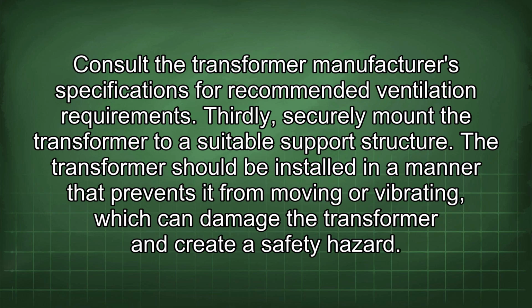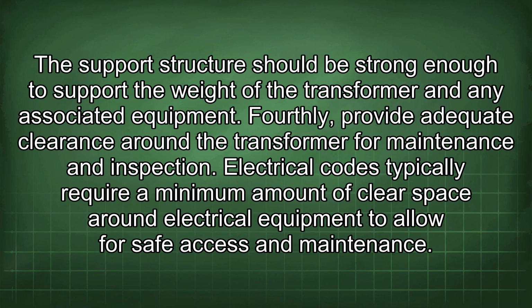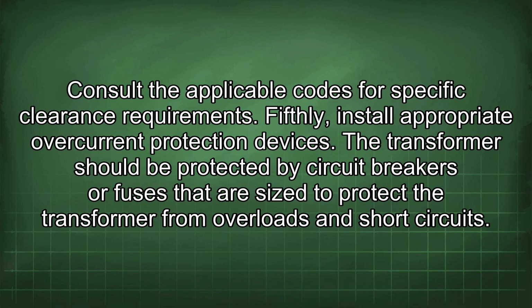Thirdly, securely mount the transformer to a suitable support structure. The transformer should be installed in a manner that prevents it from moving or vibrating, which can damage the transformer and create a safety hazard. The support structure should be strong enough to support the weight of the transformer and any associated equipment. Fourthly, provide adequate clearance around the transformer for maintenance and inspection. Electrical codes typically require a minimum amount of clear space around electrical equipment to allow for safe access and maintenance. Consult the applicable codes for specific clearance requirements.